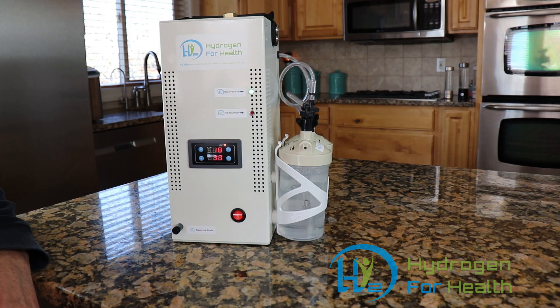Also, what most people don't know is that as a machine is used, the water in the generator heats up. This heat increases gas production and changes the parameter of the adjustable control. You might think you're breathing 450 milliliters of gas, when in fact you could be breathing a dangerous level over four point seven percent.